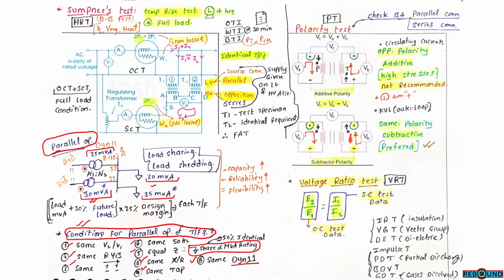conditions for parallel operation. One is V2 by V1 must be the same. So on the HV side 33 kV voltage, on the LV side 11 kV voltage. The same must be satisfied. Second, same phase sequence RYB, and this is also RYB. Same polarity. The voltage polarities will be the same on both sides. This can be identified with reference to the dot.